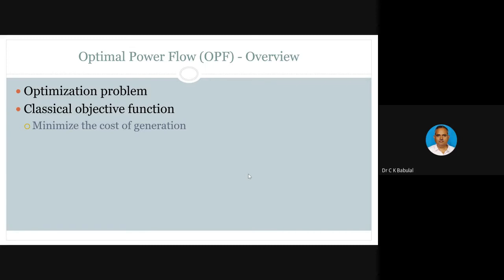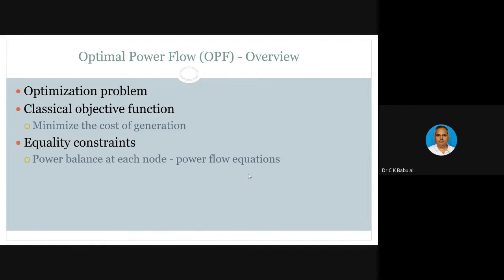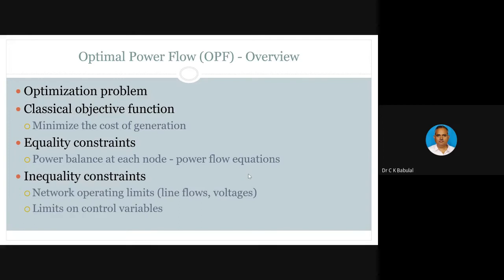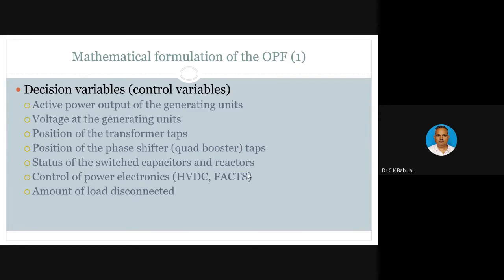It is an optimization problem, and the classical objective function is to minimize the cost of generation, though many other objective functions can also be framed. There are equality constraints and inequality constraints. The equality constraints are power balance at each node, or the power flow equations that must be solved, so solving the power flow becomes part of optimal power flow. The inequality constraints are network operating limits, like maximum possible power flows in the transmission lines, called thermal limits of the transmission line, bus voltage magnitude limits, and limits on control variables, upper and lower limits of generators. Now we'll see the mathematical formulation of optimal power flow.